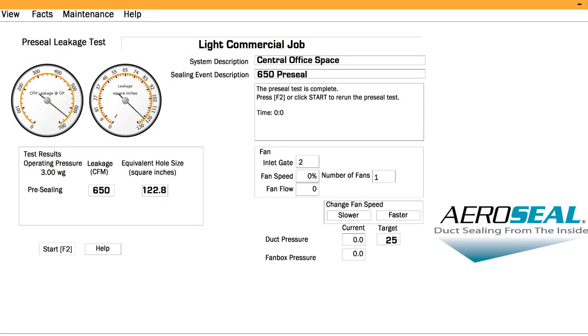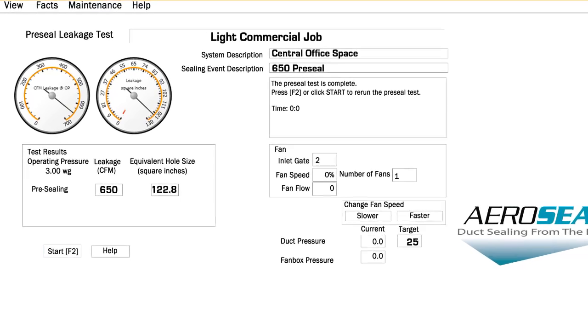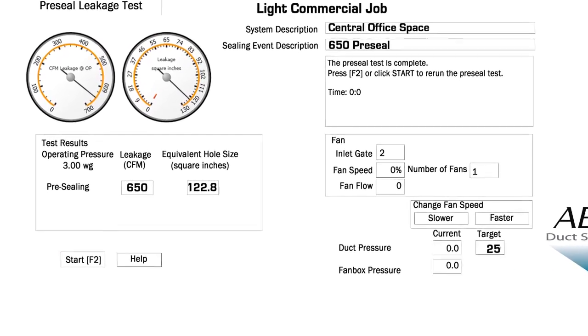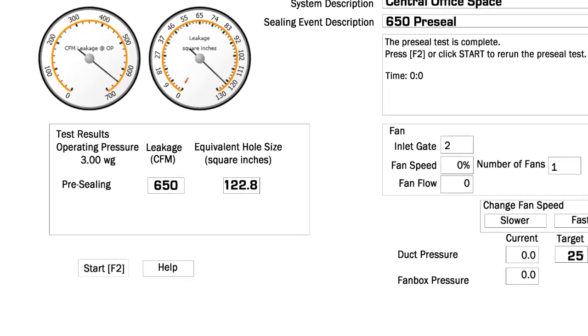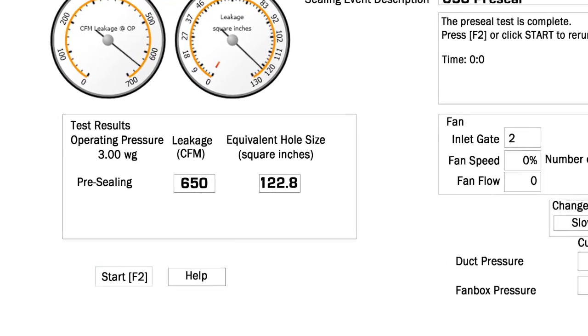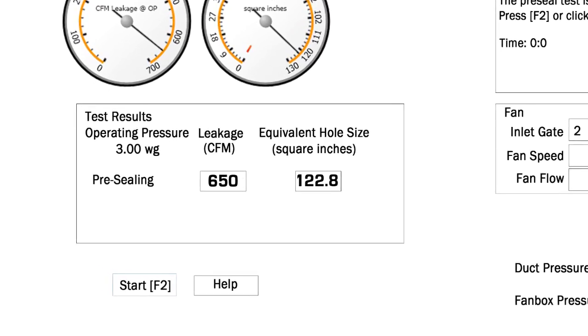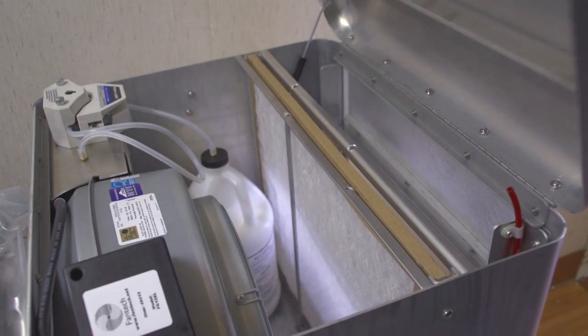The first step is to conduct a pre-seal test of your duct system being sealed. This test will tell you the initial rate of leakage prior to any sealing you perform. Once you have established the initial leakage rate, you can proceed with the sealing process. It is time to start sealing.